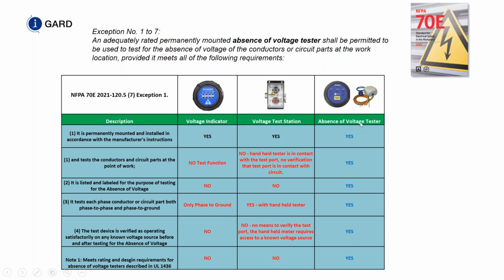So this is the I Gard absence of voltage tester. It is permanently mounted and installed in accordance with the manufacturer's instructions. Yes, all of them are permanently installed devices. These are voltage indicators, and this is a voltage test station, right? So the tests being conducted in the circuit parts of the point of work. There's no test function. 1436 requires a test function. The I Gard IAVT is the only device here that actually meets all the exceptions of NFPA 70E 1 through 7.